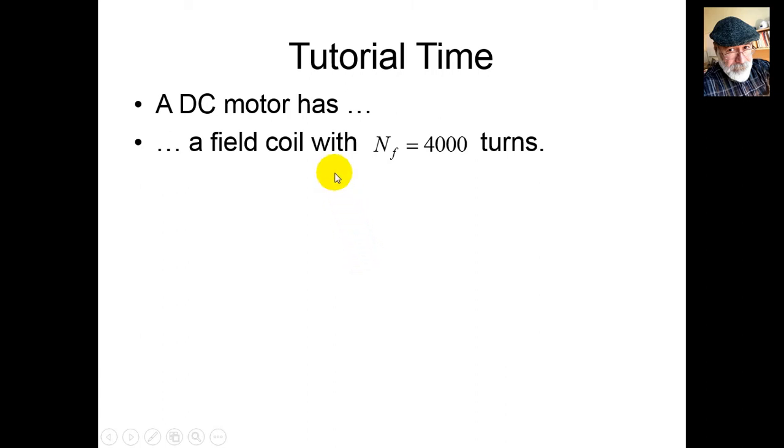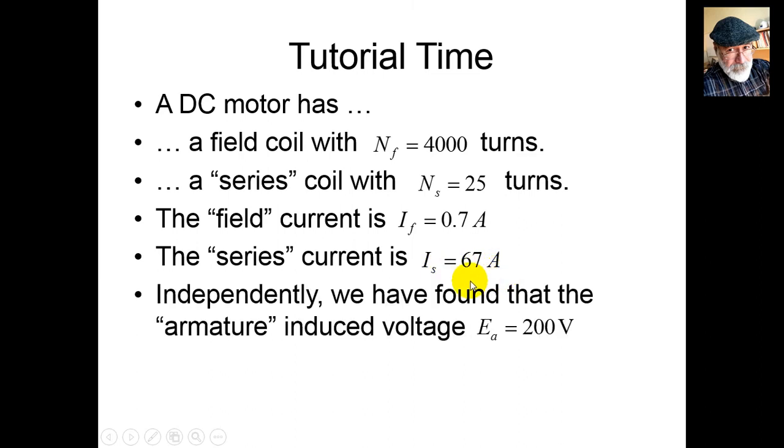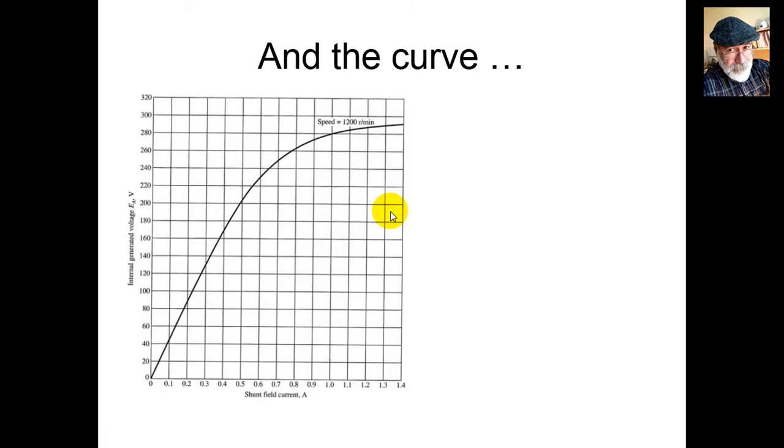Let's show how this works in a tutorial. A DC motor has a field coil with 4000 turns per pole and a series coil with 25 turns per pole. The field current IF is 0.7 amps, the series current IS is 67 amps. Independently, we've found the armature induced voltage Ea is 200 volts. What is the actual velocity of the motor?